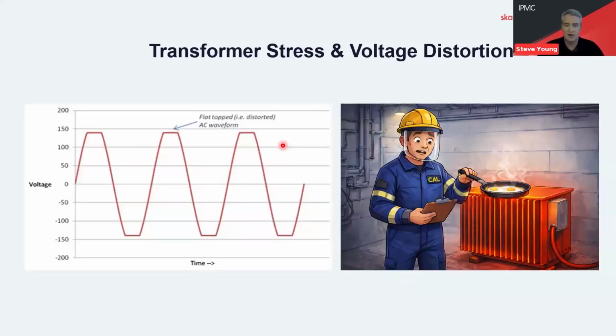Now, when we get different types of waveform distortions on the voltage, that might mean across the zero line we might have a double crossover, which is really an unwanted characteristic, particularly for electronic load-bearing equipment, and similarly with flat topping of the waveform, depending on the type of harmonic loads that we've got connected. A lot of items will fail or maloperate, if you like, if they're supplied with this flat-topped waveform. So the less current distortion we have by way of the harmonics, the less voltage distortion we're going to have. And ultimately, remember, harmonics manifest as heat and vibration, and it can be very significant.